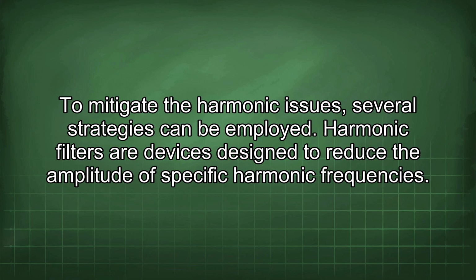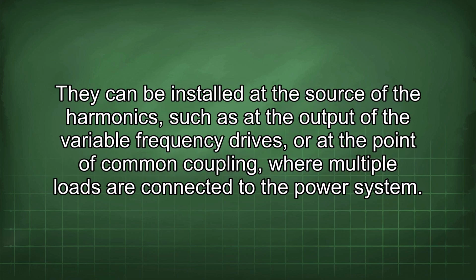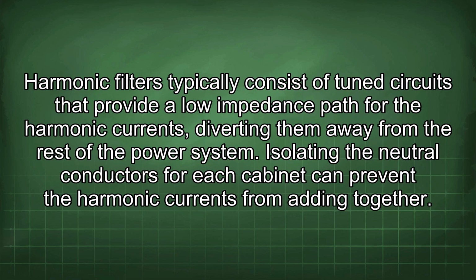Harmonic filters are devices designed to reduce the amplitude of specific harmonic frequencies. They can be installed at the source of the harmonics, such as at the output of the variable frequency drives, or at the point of common coupling where multiple loads are connected to the power system. Harmonic filters typically consist of tuned circuits that provide a low impedance path for the harmonic currents, diverting them away from the rest of the power system.